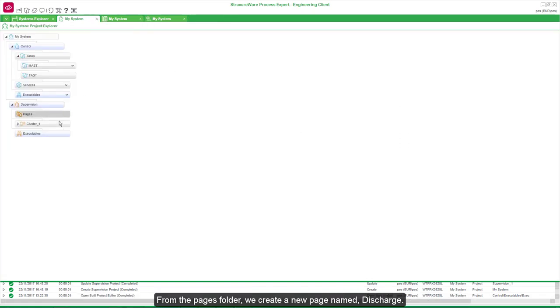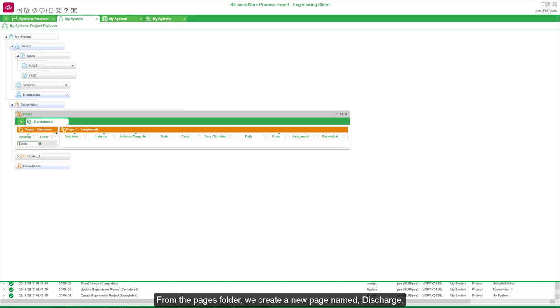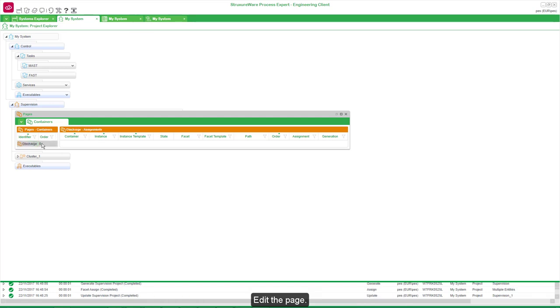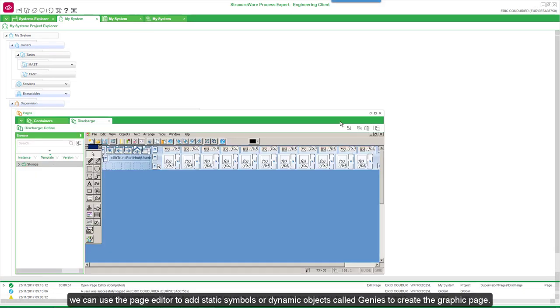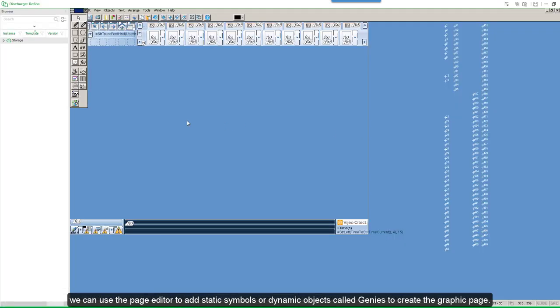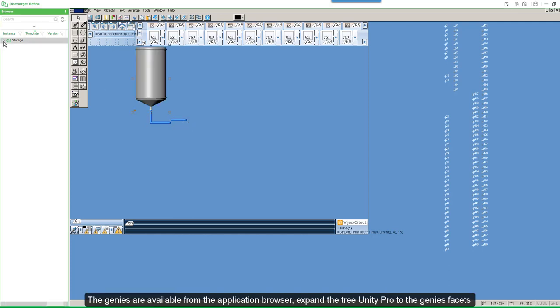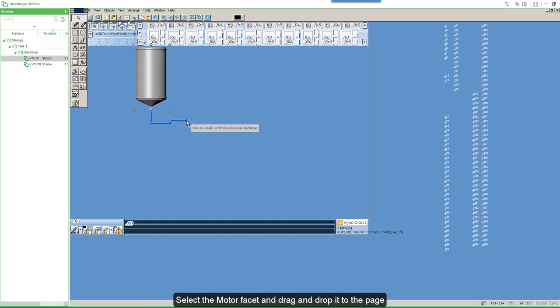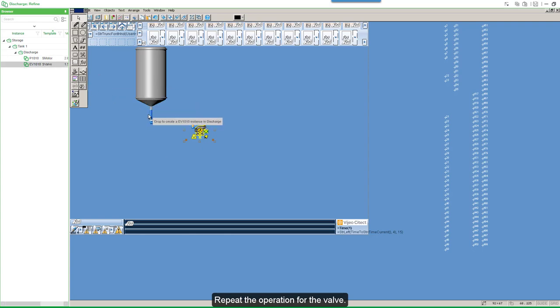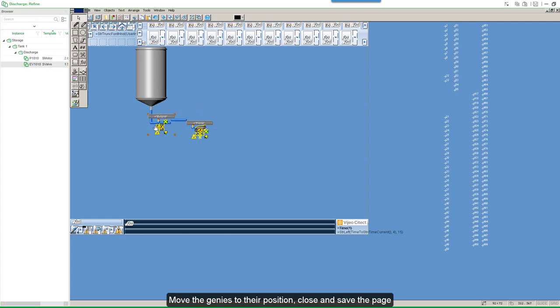From the Pages folder, we create a new page named Discharge. Edit the page. We can use the page editor to add static symbols or dynamic objects called Genies to create the graphic page. First we will add static pipes and one tank. The Genies are available from the application browser. Expand the tree, select the motor facet and drag and drop it to the page. Repeat the operation for the valve. Move the Genies to their position, then close and save the page.